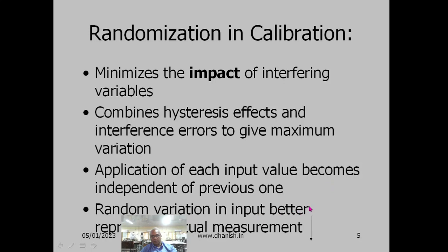Random variation in input better represents the actual measurement. When using a calibrated measuring instrument, the input variable will not always be increasing or decreasing. In a real measurement, you may get a high value at one moment and immediately a low value the next. It is not fair to use either increasing or decreasing order. The real variable will always be in random order, so when you calibrate, using random variation of input better represents the actual measurement conditions.